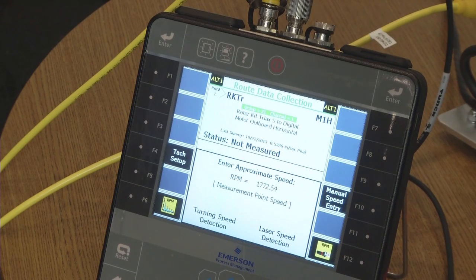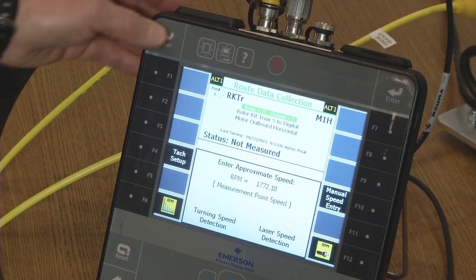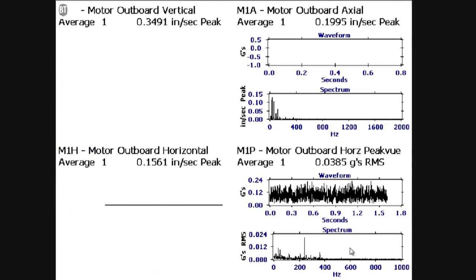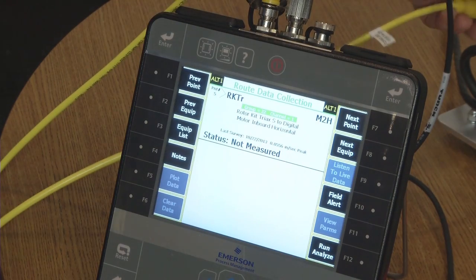Since this is a variable speed motor, the analyzer is asking me to confirm the speed from the laser speed detection. I confirm by pressing the enter button, and data collection on the three axes plus PeakVue is complete on the motor outboard. It automatically advances to the motor inboard position.